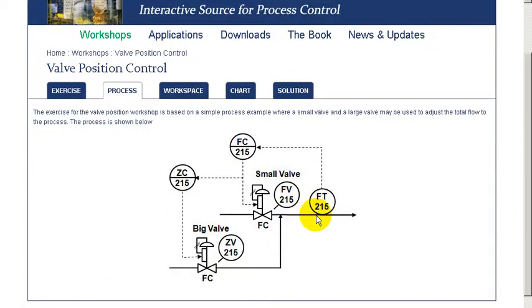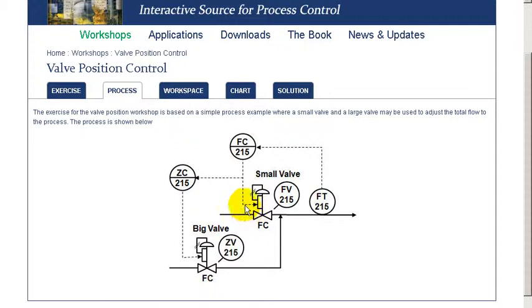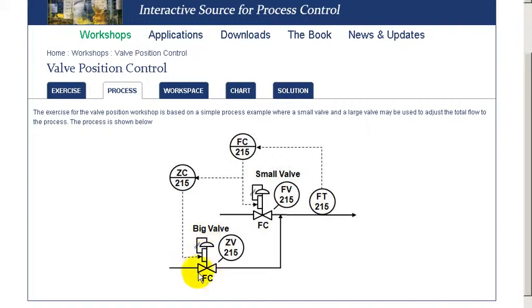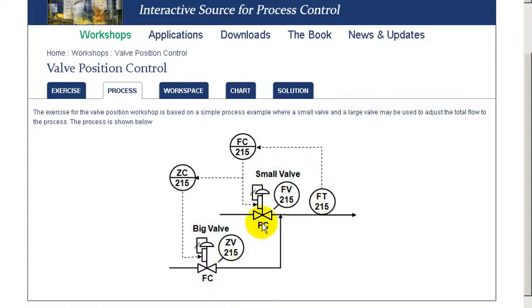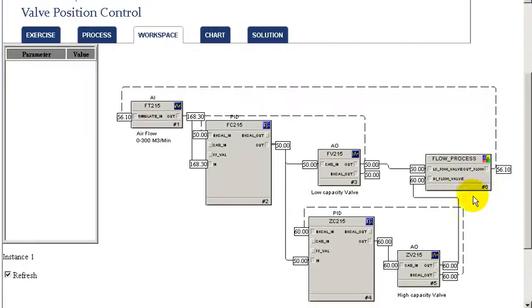In this workshop, the process we're simulating is one in which a small valve is used to precisely maintain a target flow. A large valve is then used to maintain the valve position of the smaller one to keep it within range. So the valve position controller is adjusting the larger valve to keep the smaller valve within range. Through the coordination of these two loops, we're able to precisely maintain flow over a wide range.